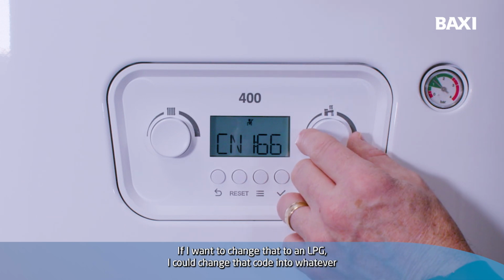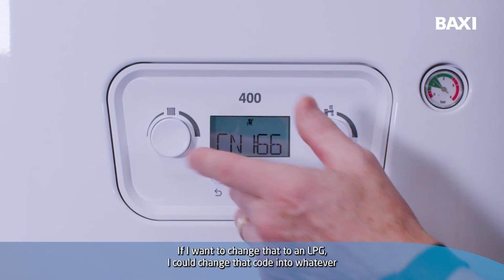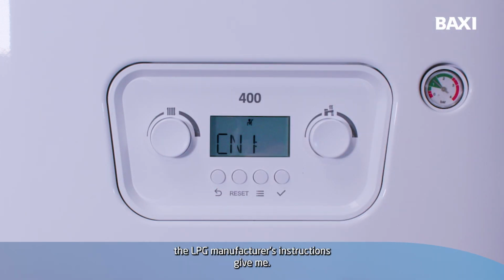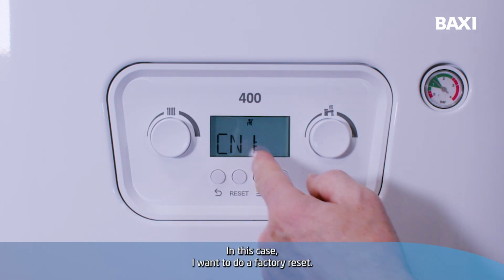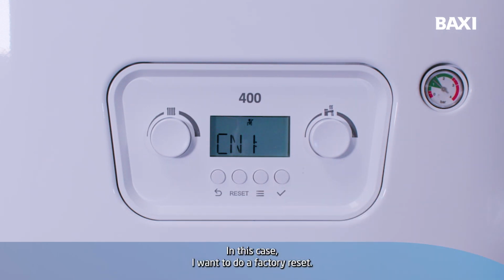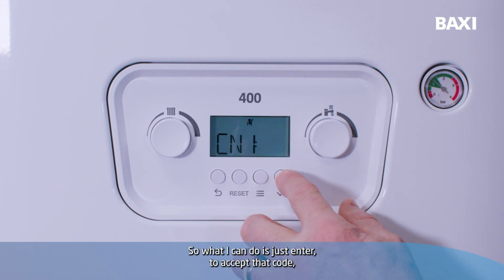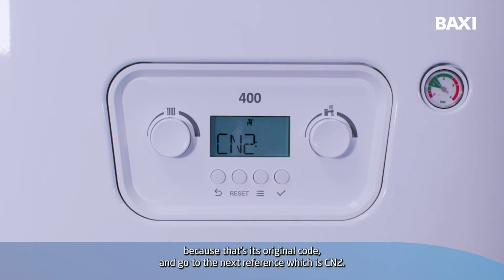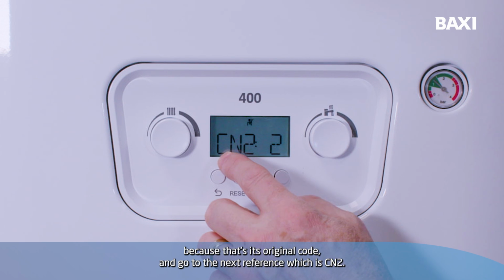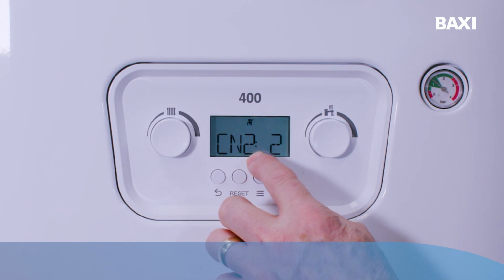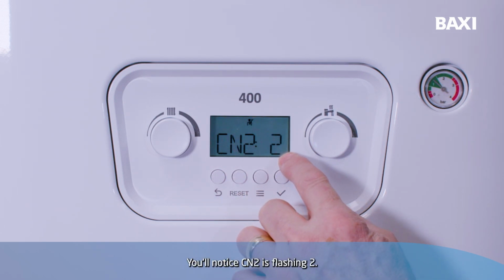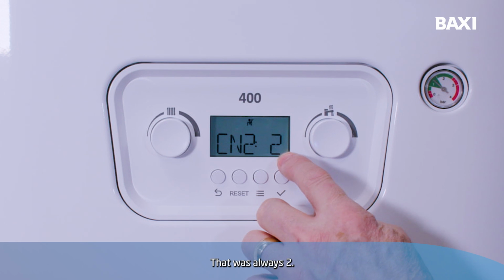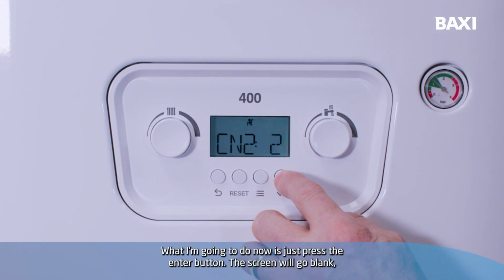If I want to change that to an LPG, I could change that code into whatever the LPG manufacturer's instructions give me. In this case, I want to do a factory reset. So what I can do is just enter to accept that code because that's its original code and go to the next reference, which is CN2. You'll notice CN2 is flashing 2. That was always 2. What I'm going to do now is just press the enter button.